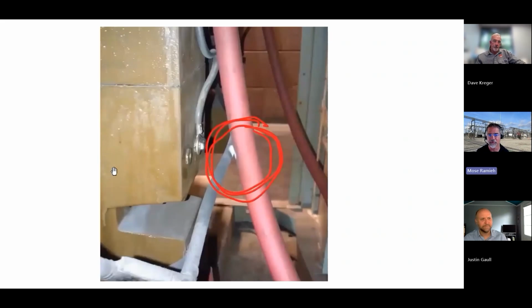Now, the potential between this cable and ground might have been 2,400 volts, but when it's in proximity to another phase, now we're talking about 4,160. So the stresses are even greater. And once again, this left uncorrected will cause an outage. It'll be an arc flash event. It will probably happen at 2:00 in the morning when nobody's around, but it could just as easily happen at 2:00 in the afternoon when somebody's in the switchgear room doing their sweeping.